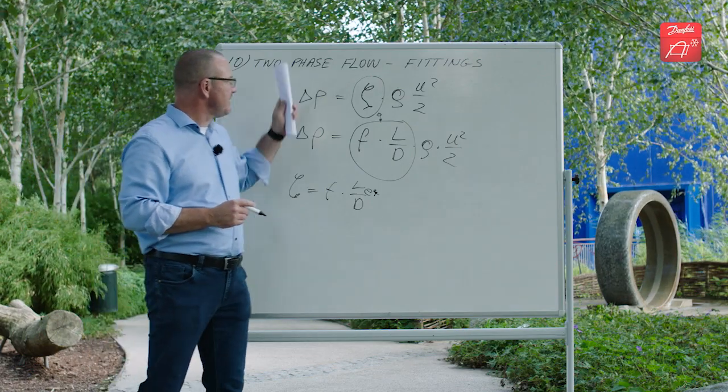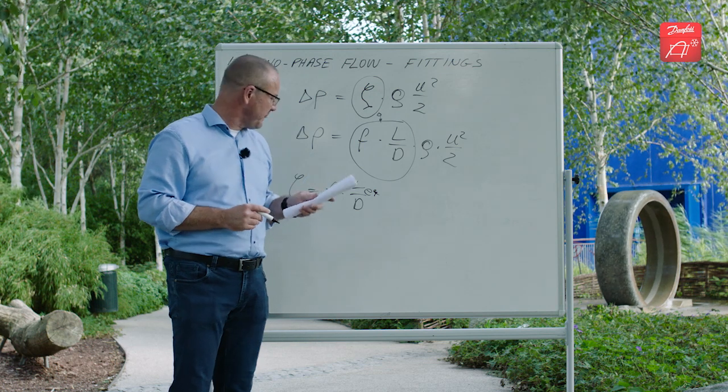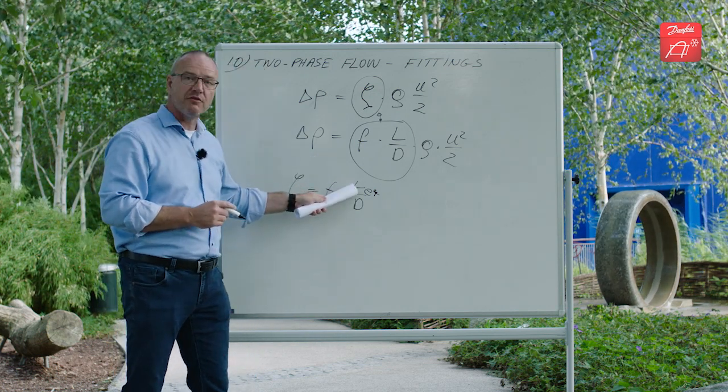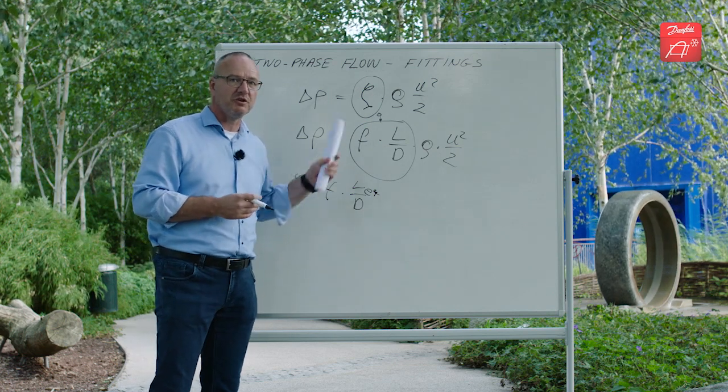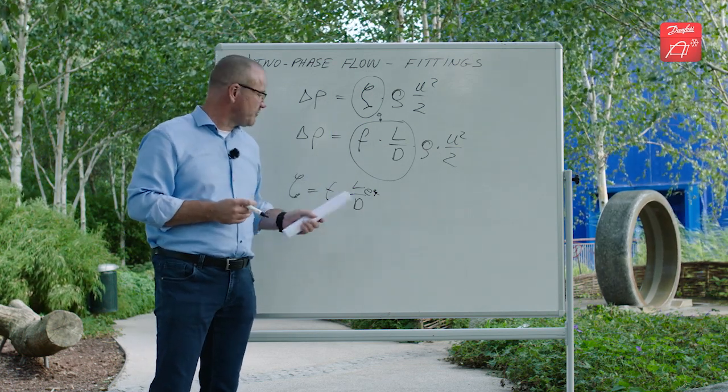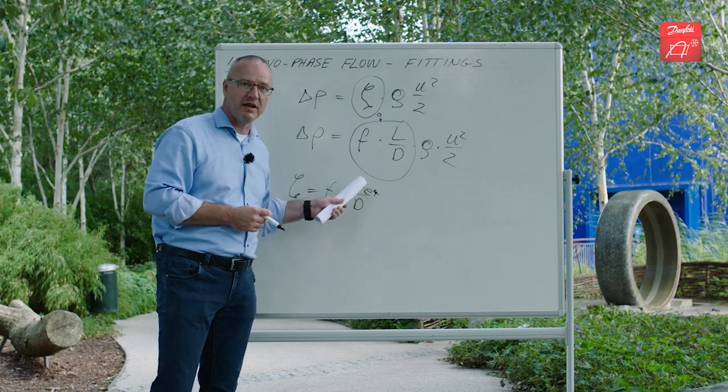So the exercise here when you talk about two-phase flow is actually to calculate this equivalent length and then use the Friedel correlation that we showed you last time to calculate the pressure drop in a pipe of equivalent length.